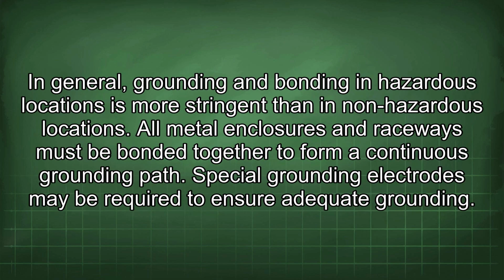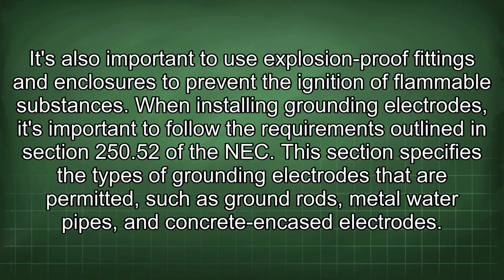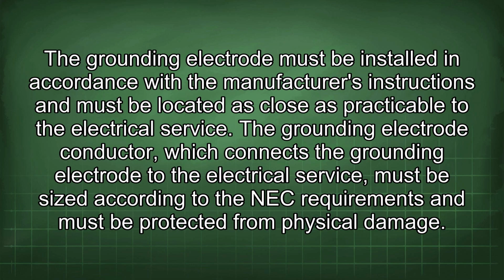In general, grounding and bonding in hazardous locations is more stringent than in non-hazardous locations. All metal enclosures and raceways must be bonded together to form a continuous grounding path. Special grounding electrodes may be required to ensure adequate grounding. It's also important to use explosion-proof fittings and enclosures to prevent the ignition of flammable substances. When installing grounding electrodes, it's important to follow the requirements outlined in Section 250.52 of the NEC. This section specifies the types of grounding electrodes that are permitted, such as ground rods, metal water pipes, and concrete-encased electrodes. The grounding electrode must be installed in accordance with the manufacturer's instructions and must be located as close as practicable to the electrical service.